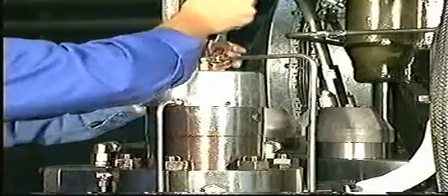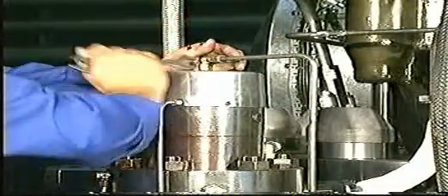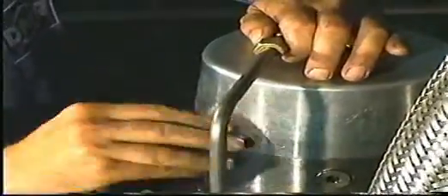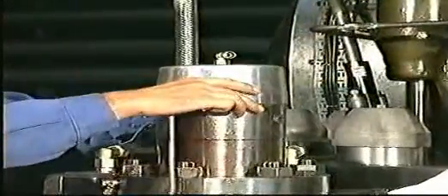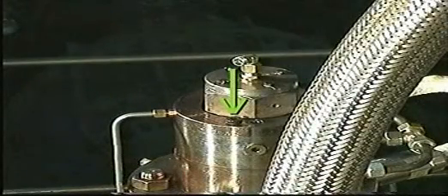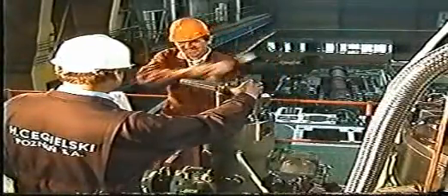The actual fuel pump lead must be determined before turning the cams. Make sure that the reversing links are in the head position. Disconnect the air pipe and remove the cover from the puncture valve. Remove the plug screws to provide access for the measuring tool. Remove the puncture valve.